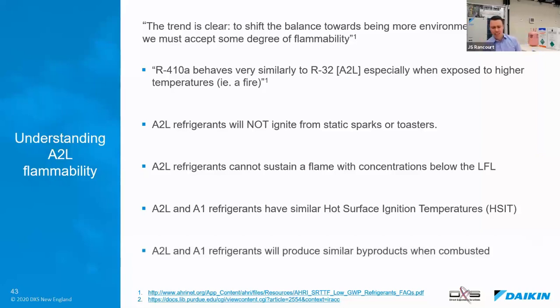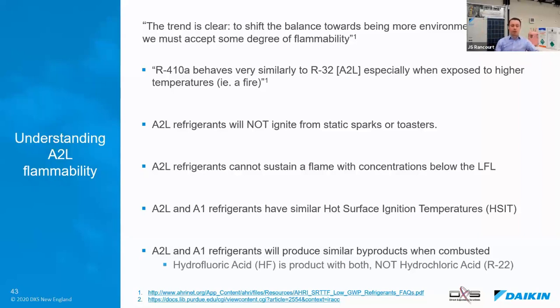But one of the thoughts is, hey, isn't the issue the byproducts? If there is a fire in the building, yeah, okay, R410A burns, but what if R32 burns? How about the byproducts? Well, both R410A and R32 generate hydrofluoric acid. They do not generate hydrochloric acid, which R22 used to in a fire, and that's the big issue. So the byproducts of R32 are similar. It makes sense because R410A is made of half R32.